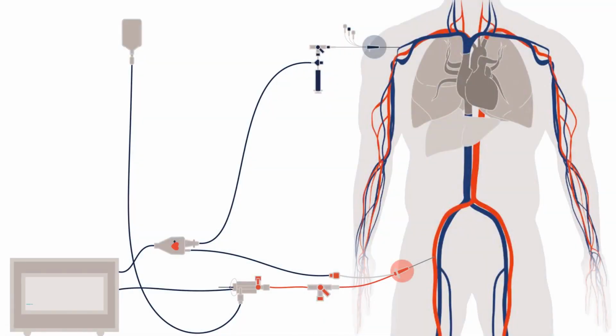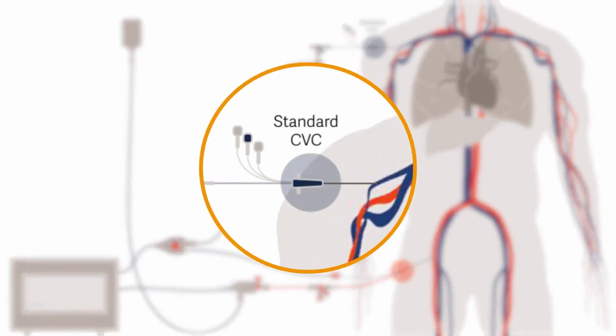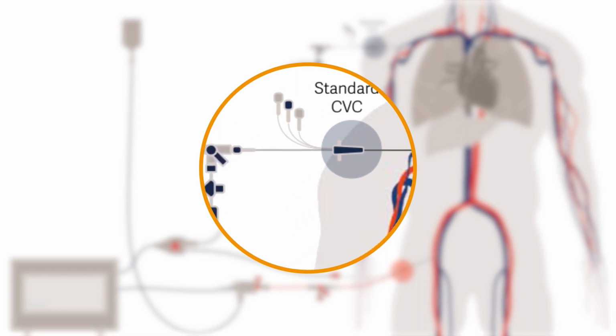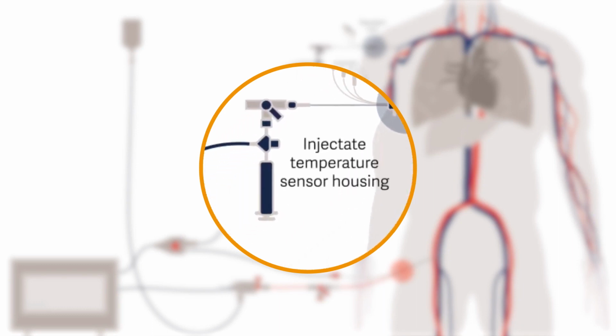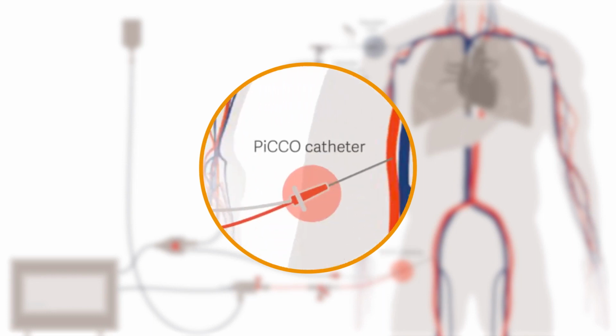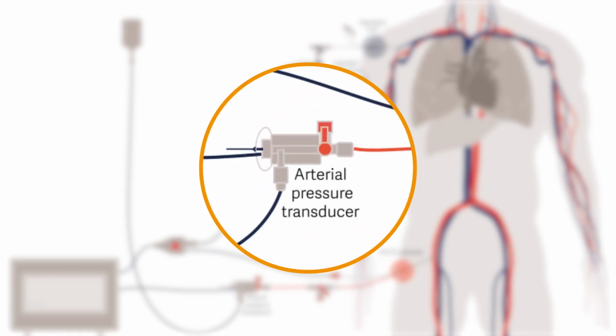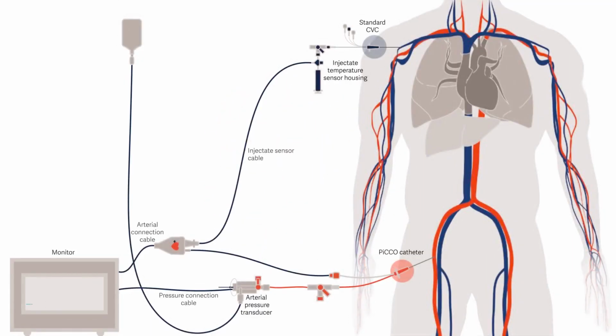To use PICCO technology, properly set up its equipment. At the patient's side, PICCO requires a standard central venous catheter, or CVC, with a connected injectate temperature sensor housing, an arterial thermodilution catheter, or the PICCO catheter with an integrated temperature sensor at the tip, and a connected PICCO pressure monitoring kit. All of these are connected to the monitor using cables.